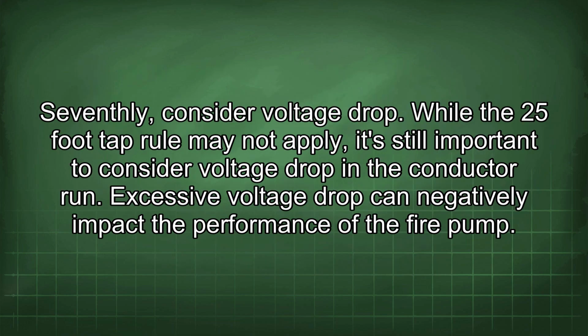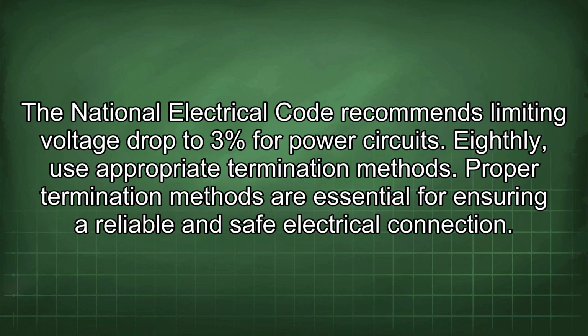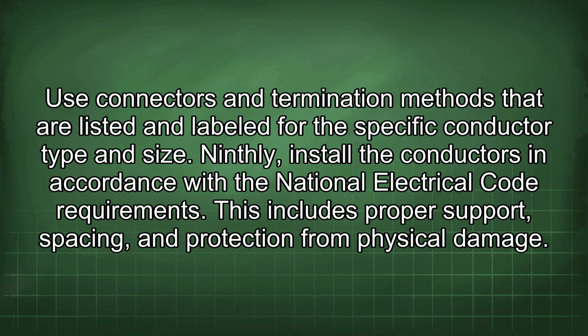Seventhly, consider voltage drop. While the 25-foot tap rule may not apply, it's still important to consider voltage drop in the conductor run. Excessive voltage drop can negatively impact the performance of the fire pump. The National Electrical Code recommends limiting voltage drop to 3% for power circuits. Eighthly, use appropriate termination methods. Proper termination methods are essential for ensuring a reliable and safe electrical connection. Use connectors and termination methods that are listed and labeled for the specific conductor type and size.